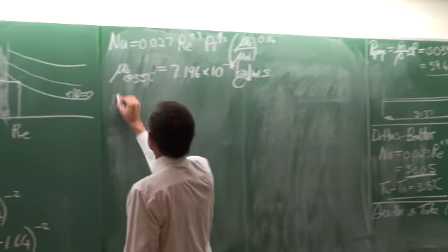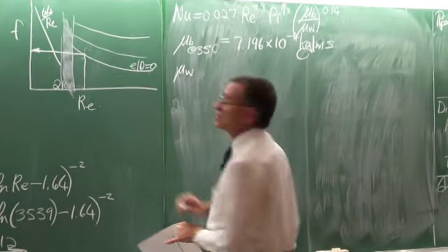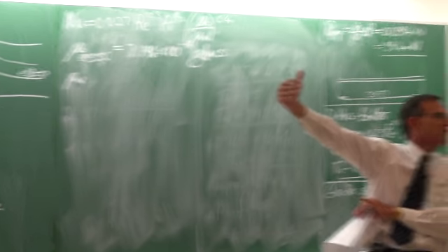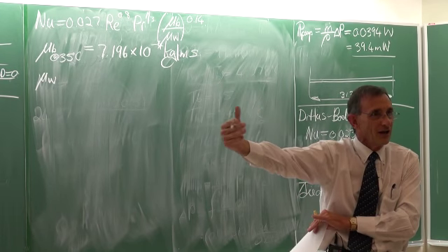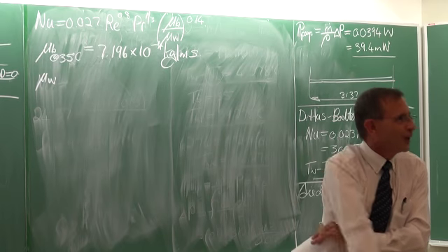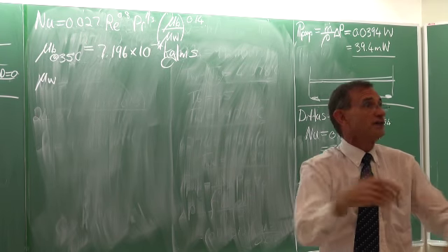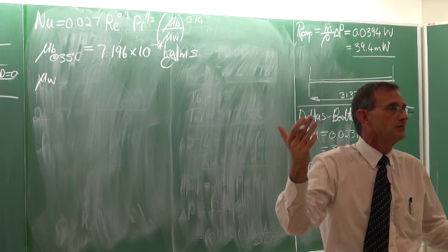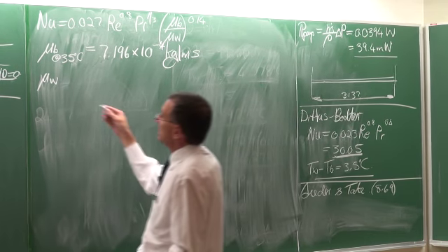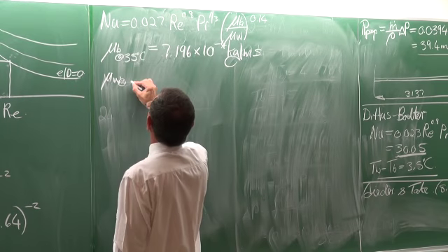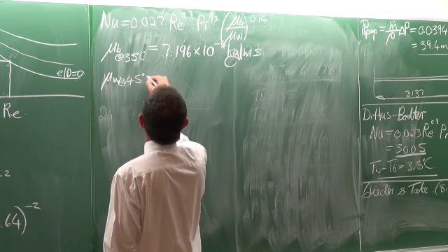Now the problem is, what is the viscosity on the wall? If you've done this, then you know, typically, it's about 3 to 4 degrees higher. But if you haven't done it, you do not know. So you have to either guess 5 degrees, 10 degrees higher. So you can go and select maybe 45.